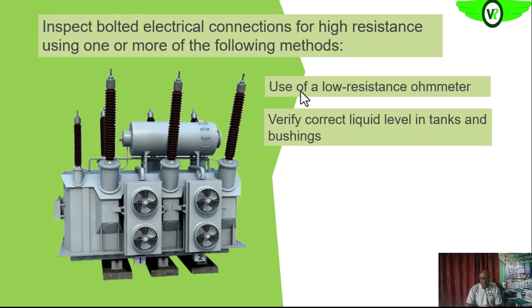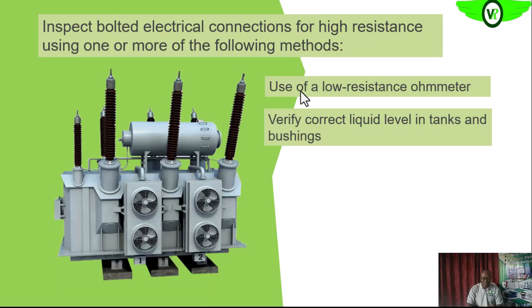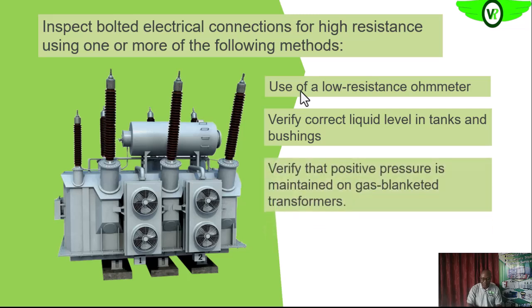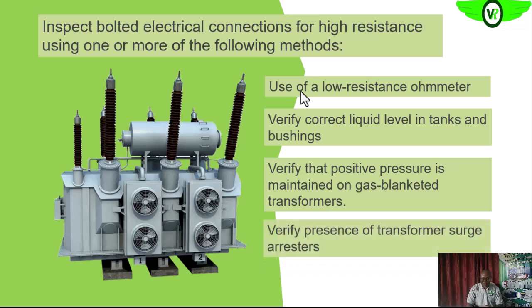Then the level of liquid in the tank and in the bushing, if it is the liquid-filled, oil-filled bushings that are used on the transformers. So we want to check that we have the appropriate levels in those pieces of equipment. So the pressure switch and, okay, we also want to ascertain that the blanket gas in the transformer, we have enough in it to maintain the positive pressure. Okay, so we want to verify that positive pressure is maintained on the gas blanket transformers. We want to verify the presence of the surge arrestor. We want to look and be sure that we have surge arresters, okay, on the transformer.